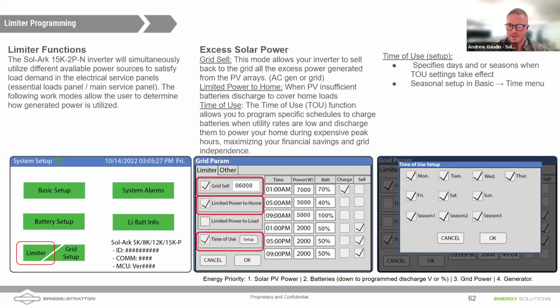So grid sell is exactly as it sounds. It's how much excess PV production that you would export to the grid. So with our PCS certification, we can reduce that or turn it off to meet requirements from the utility. Limited power to home is going to instruct the Sol-Ark to utilize the external CTs to meter upstream loads, to be able to meter what's going on external to the Sol-Ark, and also be able to measure how much excess PV would be going to that other panel without pushing it to the grid, and we can also use it for discharging the battery to cover loads in those other panels as well.